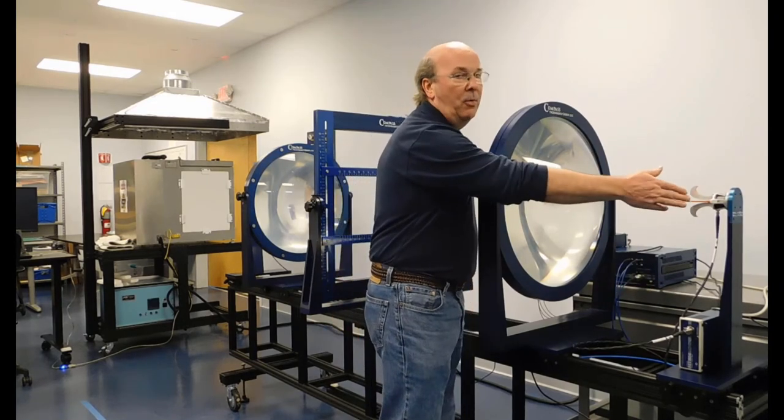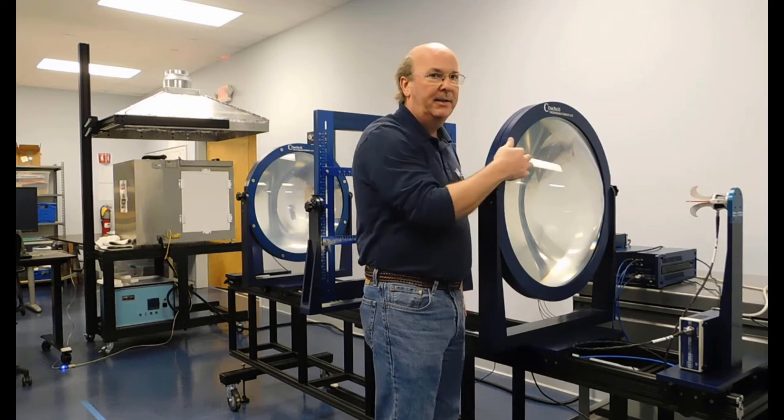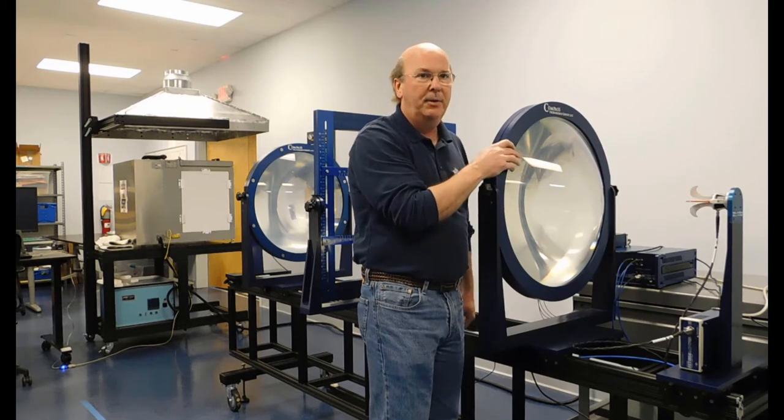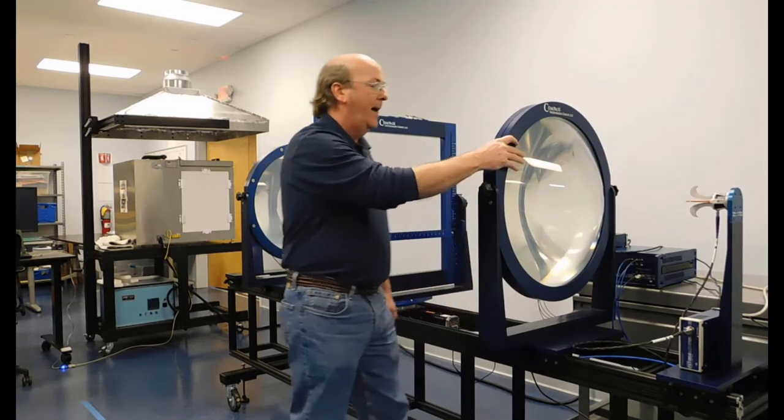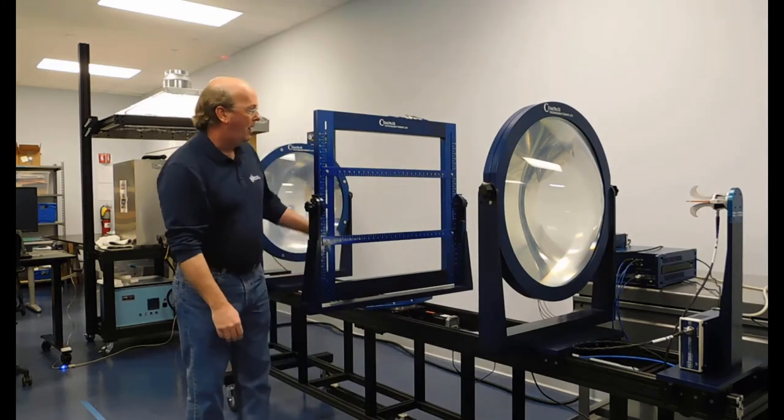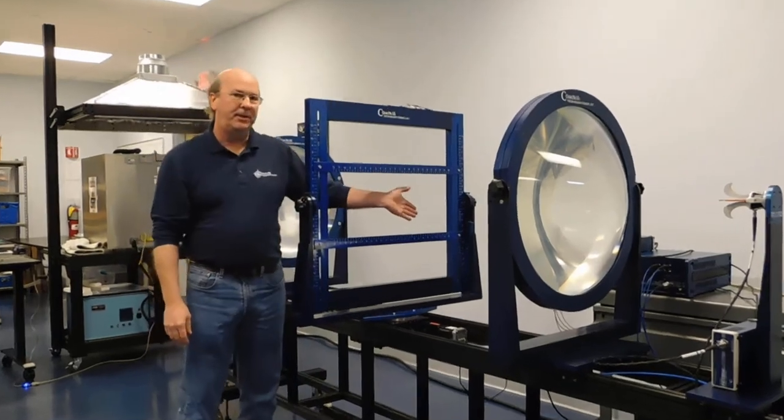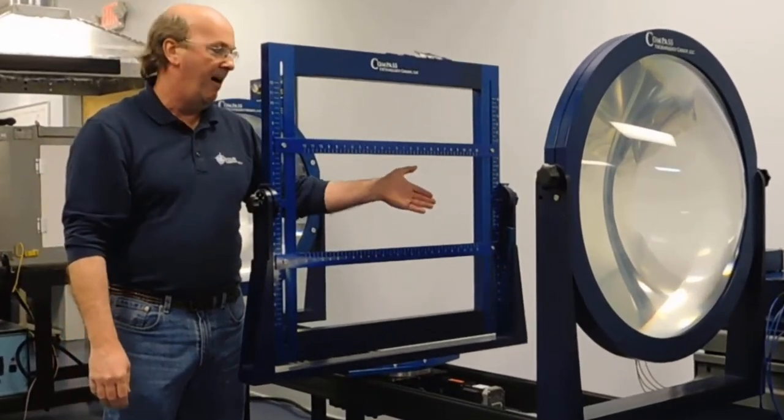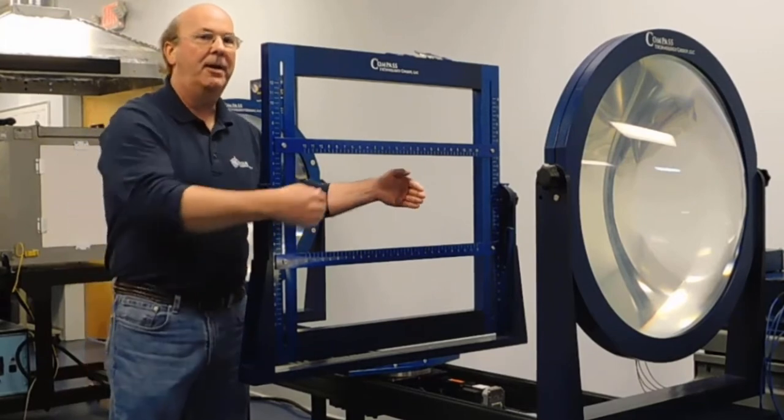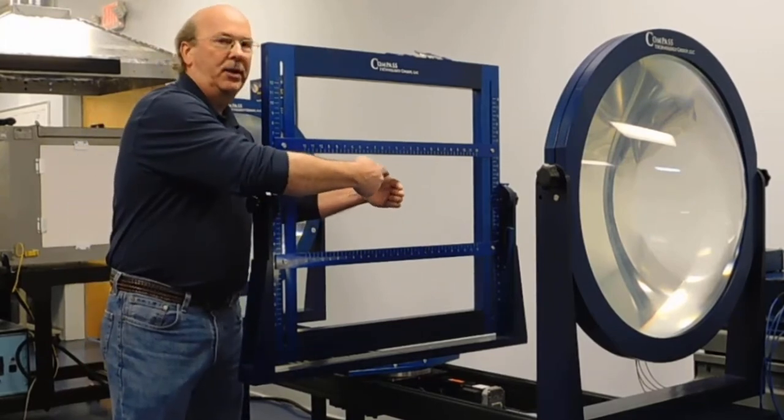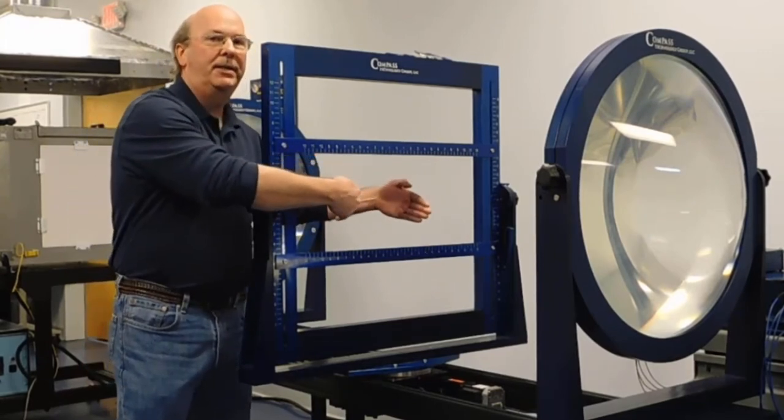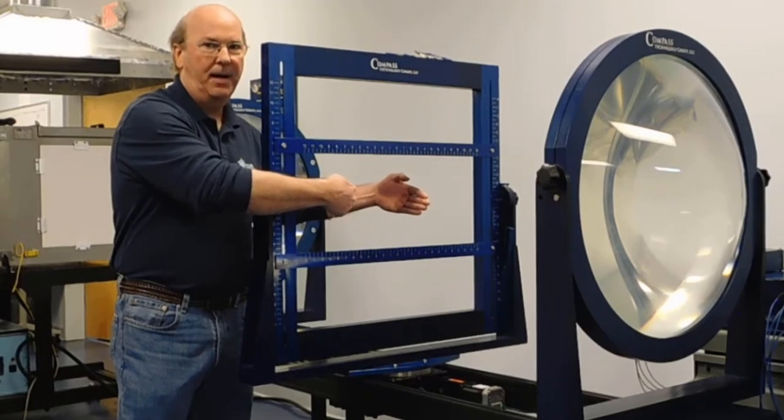The energy coming from the horn illuminates a lens. In this case we have a dielectric lens made from Rexalite and the lens focuses the energy from the horn onto the sample position here in the middle. In the middle we have a flat phase front and we have a confined beam so that we don't illuminate the edges of the specimen and don't have edge diffraction problems.